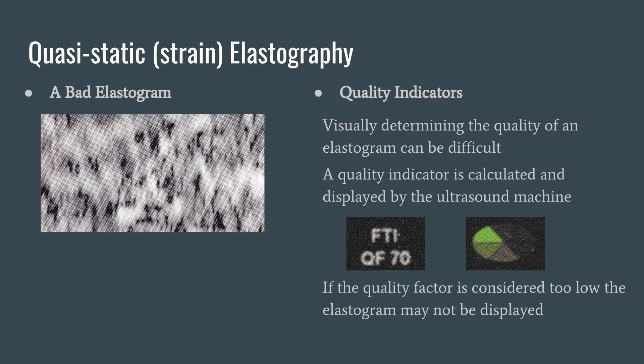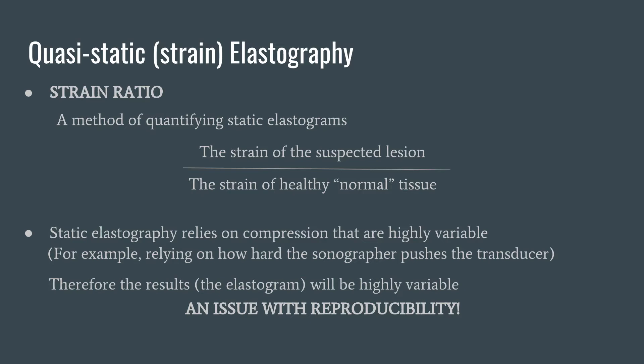Even if the displayed elastogram was considered appropriate, we would then have to determine whether an area of tissue is stiff. Some people didn't like making that decision by eye and ended up coming up with a quantitative way — a way of using numbers — to decide whether a part of tissue was stiff, being a potential lesion, or not. That is the strain ratio: a ratio of the strain of the suspected lesion divided by the strain of healthy tissue. The user would pick a point on the suspected lesion and then a point of healthy tissue, with popular choices being fat or skeletal muscles, giving the user a number.